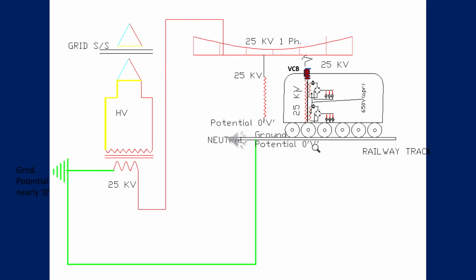The 25 kV we are receiving from the pantograph is fully dropped across the winding, and the other end of the winding is at ground potential, 0 volt. That means fully across this winding is approximately 25 kV. It may vary. Now from this main winding we are taking near about 650 volt supply, and with the help of a bridge rectifier we are converting it into DC.